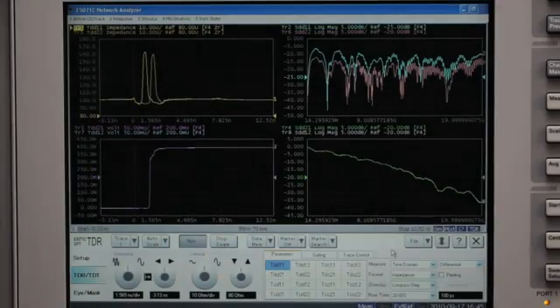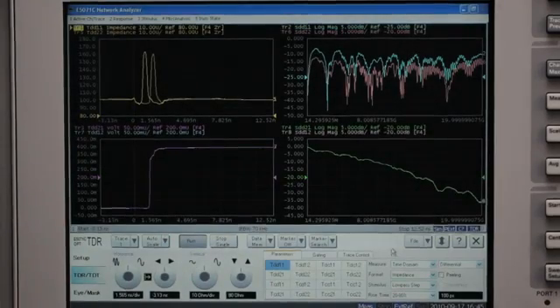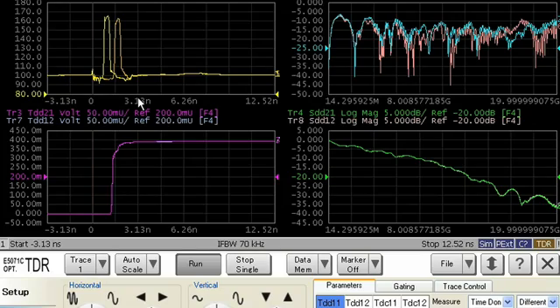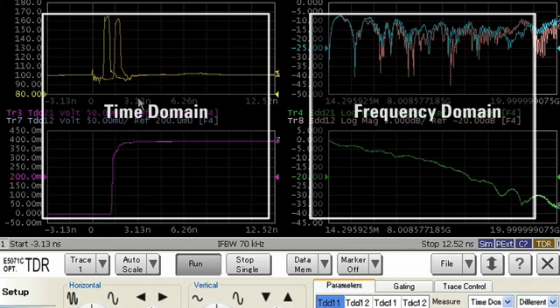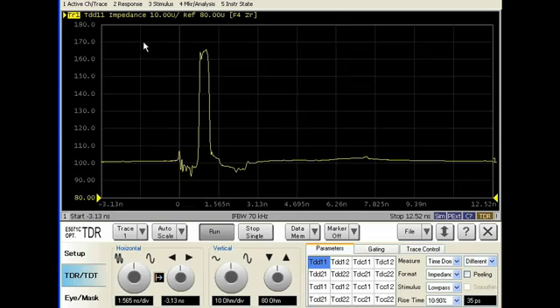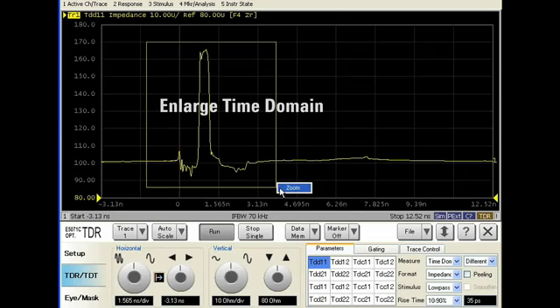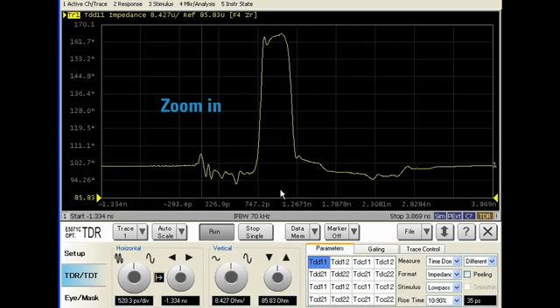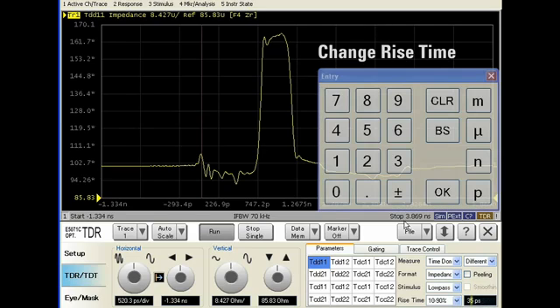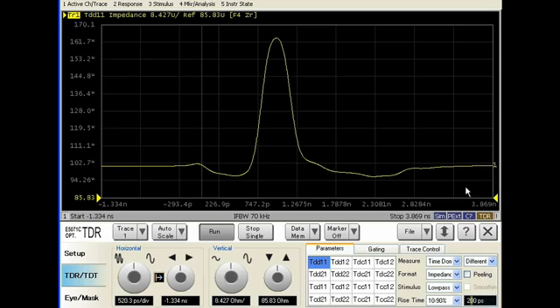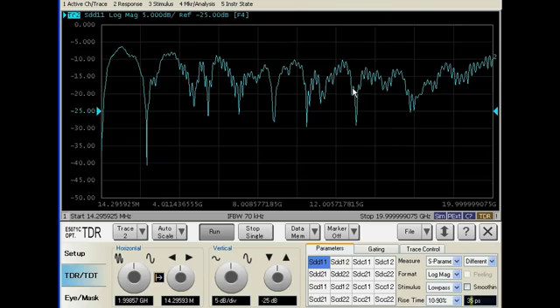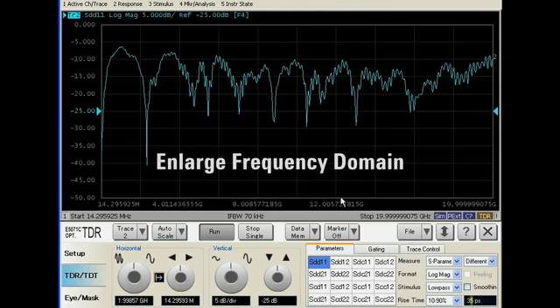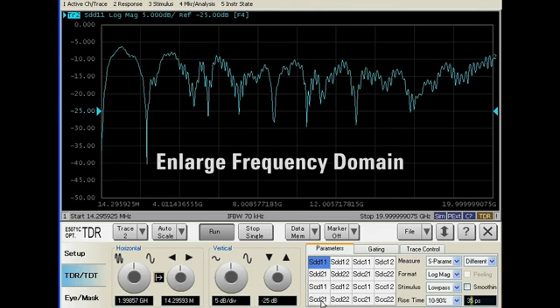What's more, with ENA Option TDR, the user interface is always smart. Time domain and frequency domain is displayed on one screen. And you can zoom in on either one at the touch of a button. You can change parameters such as rise time for time domain or mode conversion for frequency domain at any time.